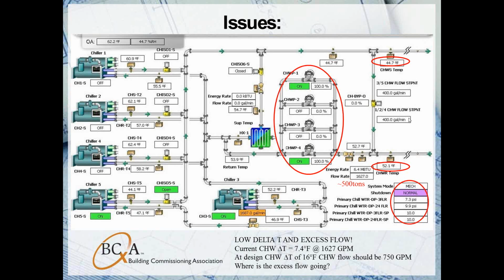You'll also notice here that we're running low delta T, about 7 or 8 degrees between supply and return. That's a fairly common problem, but in this situation, it's exacerbating the part load operation on the series counterflow chillers.